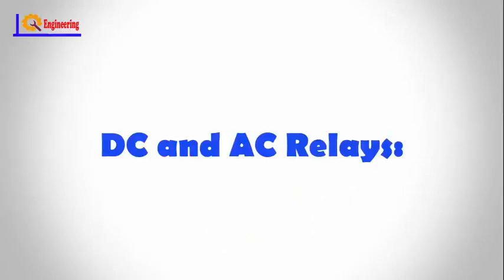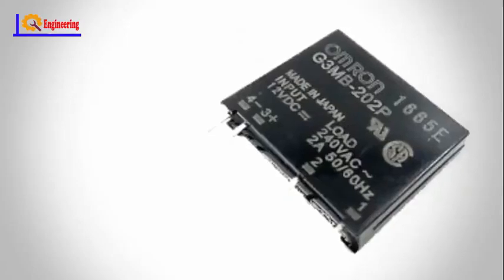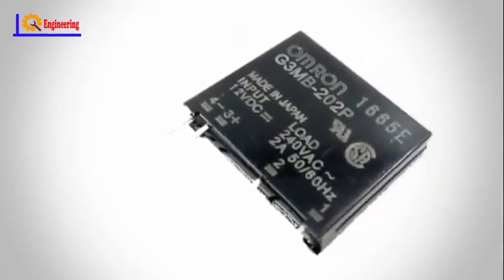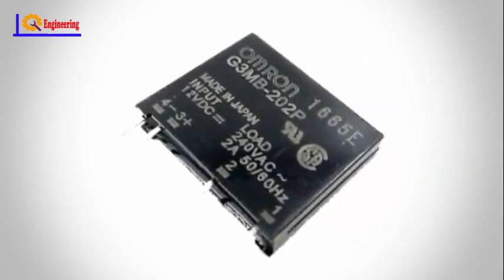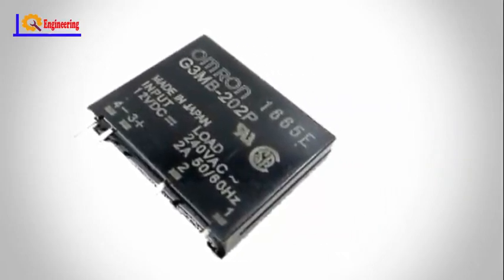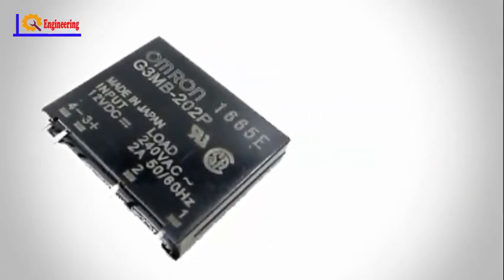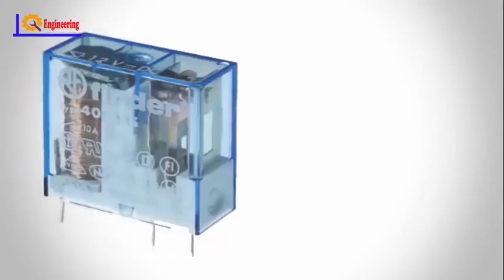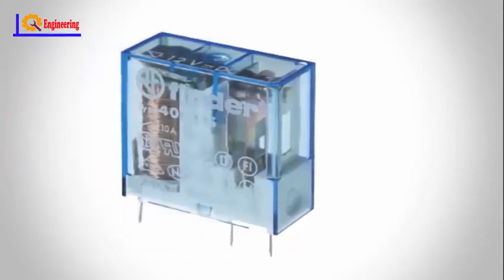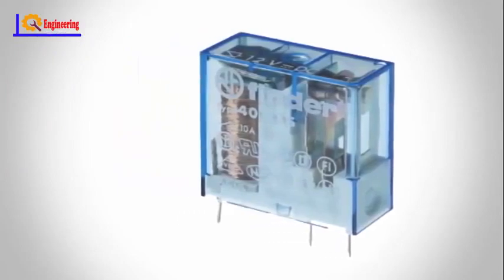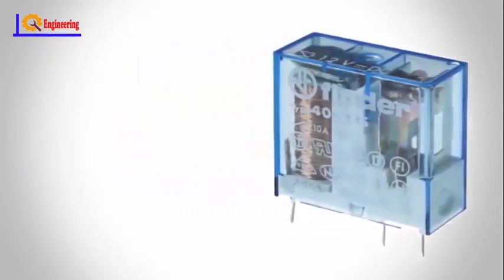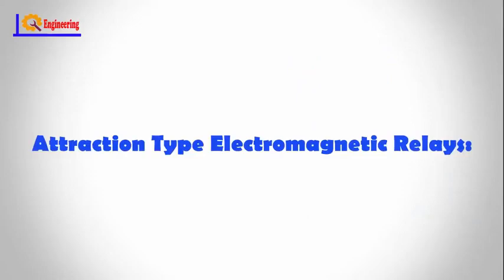DC and AC relays. Both AC and DC relays work on the same principle of electromagnetic induction, but the construction is somewhat different and also depends on the application for which these relays are selected. DC relays are employed with a freewheeling diode to de-energize the coil, and the AC relays use laminated cores to prevent eddy current losses.